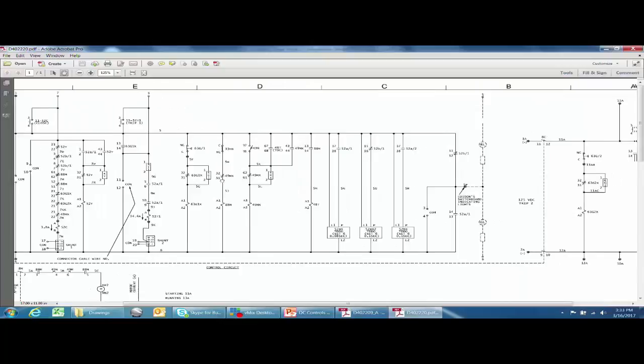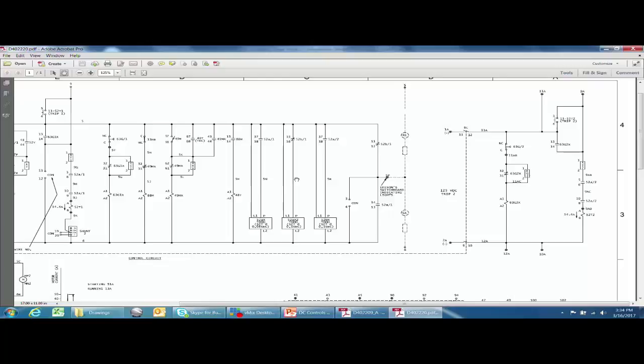On the transmission system, most circuit breakers have two trip coils. This is the second trip coil, and notice that it gets its own DC bus — its own control voltage.